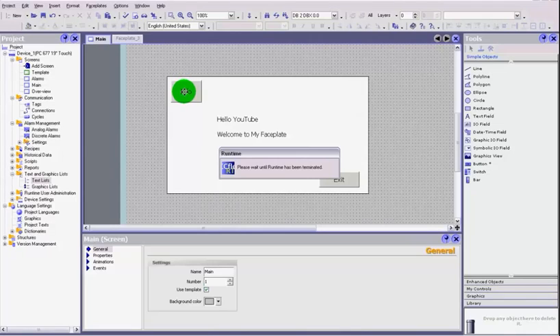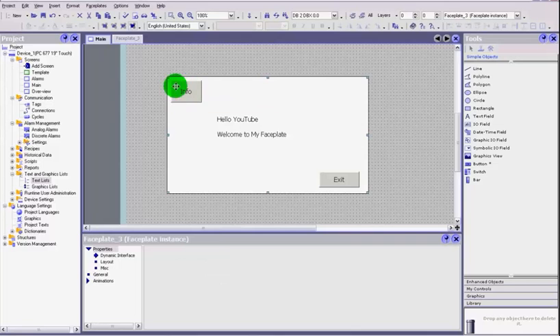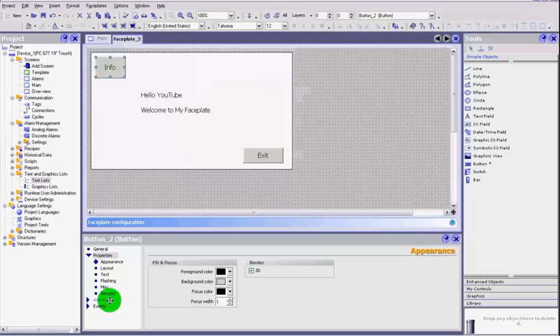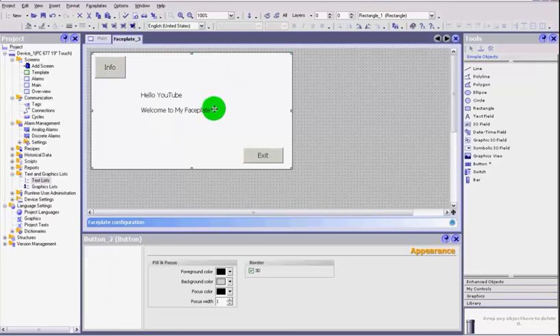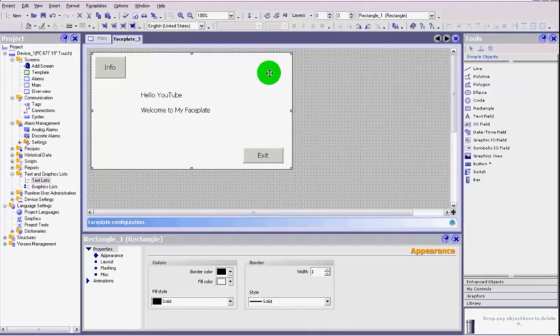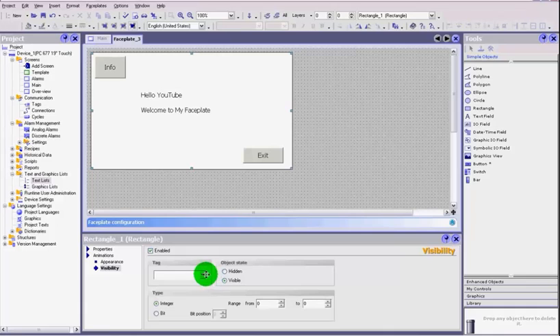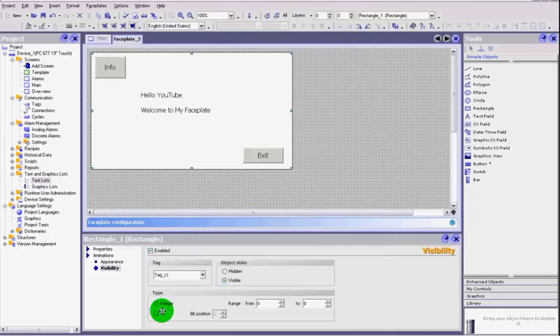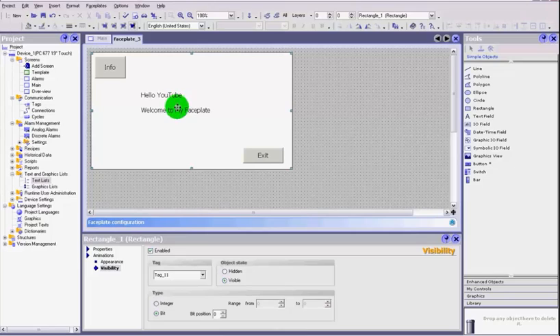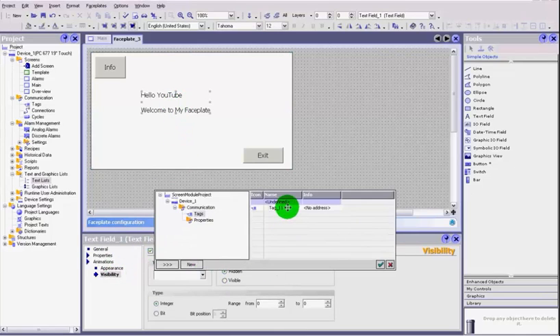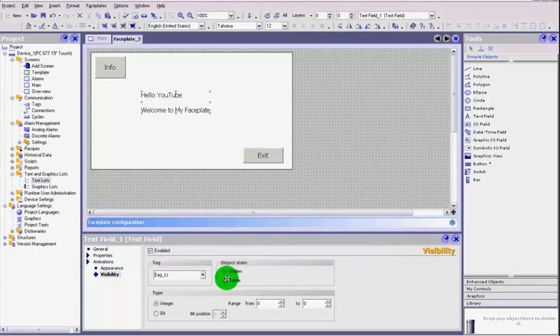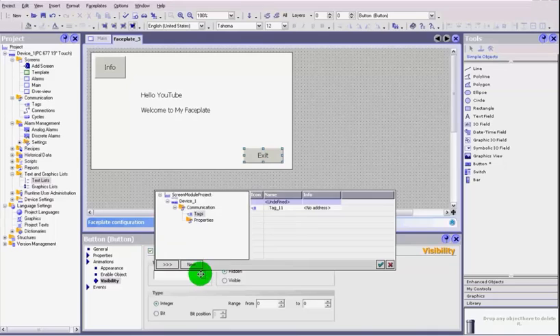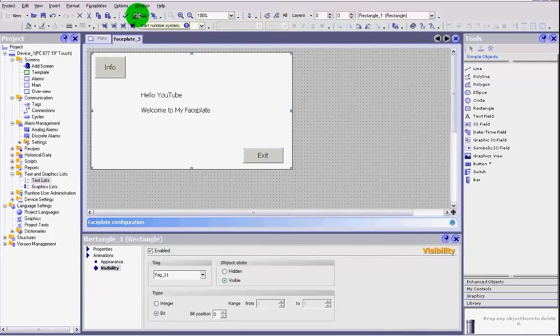So what we are going to do is, we have already created that when that button on the faceplate sets up a bit and sends that bit high. We are going to first select the rectangle, we are going to do animations, visibility, click enabled, click visible when tag eleven is true. Make sure that we set the bit so that it gets rid of all of these things. And we are going to repeat the same thing for every point on that faceplate, including the button.